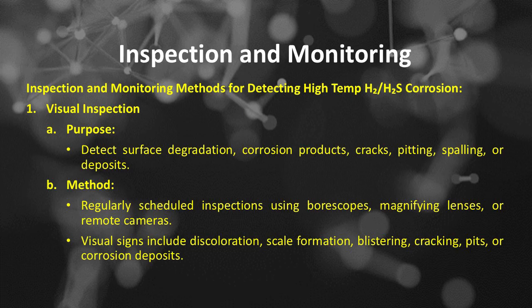Number 1 is visual inspection. This is purposed to detect surface degradation, corrosion products, cracks, pitting, spalling, or deposits. The methods of visual inspection include regularly scheduled inspections using borescopes, magnifying lenses, or remote cameras. Visual signs include discoloration, scale formation, blistering, cracking, pits or corrosion deposits.